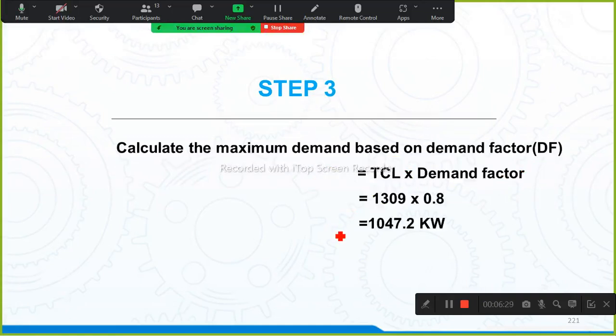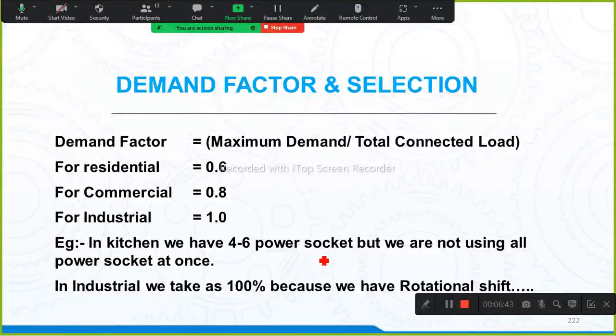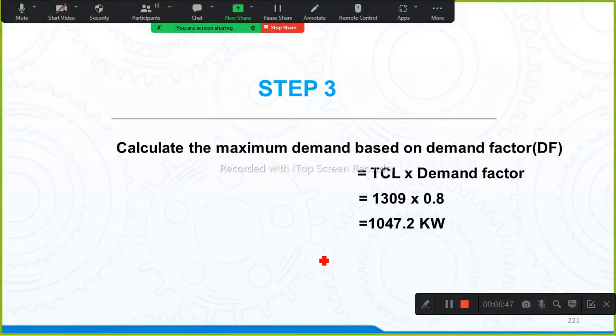Okay. Now step 3. What is step 3? Calculate the maximum demand, MD, based upon the demand factor of the building. Now what is this demand factor? Demand factor is defined as maximum demand divided by total connected load. What does demand factor mean?